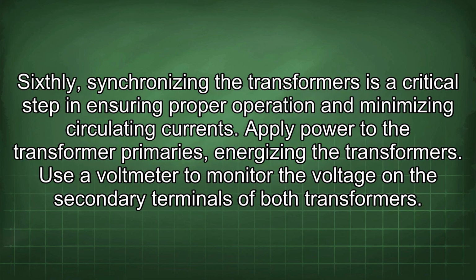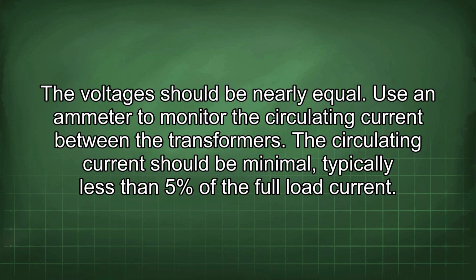Sixthly, synchronizing the transformers is a critical step in ensuring proper operation and minimizing circulating currents. Apply power to the transformer primaries, energizing the transformers. Use a voltmeter to monitor the voltage at the secondary terminals of both transformers. The voltages should be nearly equal.